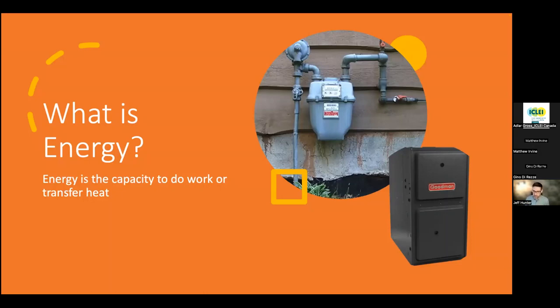Now, the actual output of that furnace is going to be reflected more by its efficiency. So we learned from Matt as well that he gave a good efficiency rating of 98%. And so that's a sticker rating. That furnace at 98% can convert 98% of the 100,000 BTUs into usable heat into the space. So that's one way to look at it. The other way is to say that what we're actually doing with that furnace is trying to extract the chemical energy that's stored in the natural gas that we're feeding, or propane or fuel oil, whatever, and convert. We're converting that chemical energy into useful thermal energy at that rate of 100,000 BTUs per hour.